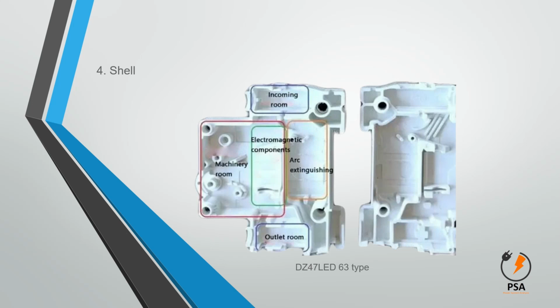The housing size is in line with industry standards. In order to unify standards and improve processing efficiency, circuit breakers below a certain rated current will use the same shell, contacts, and terminals. The maximum rated current that this enclosure can pass is the frame-level current. In this example, 63 in the model DZ47 LED 63 means that the current of the shell frame of this series is 63A. After the shell is disassembled into the left and right halves, it can be seen that most of the 2 halves are symmetrical. According to the function, the internal space can be roughly divided into 4 rooms.